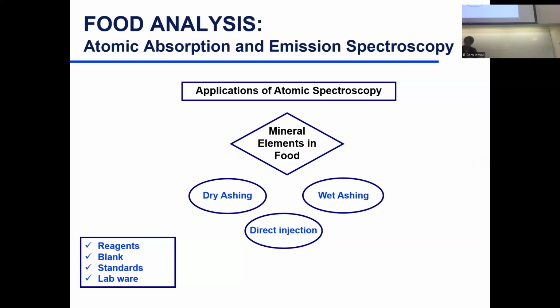So calcium forms these big molecules with a lot of phosphates interacting. So it's a really large molecule, and it won't go into the flame. It won't stay in solution. It's so big, it might just precipitate out, linger on the plastic or glass of your container, and not make it to the flame. So you will have underestimation of calcium.